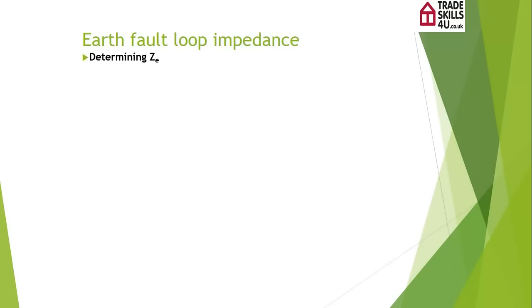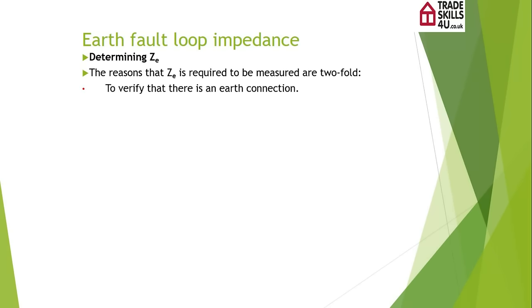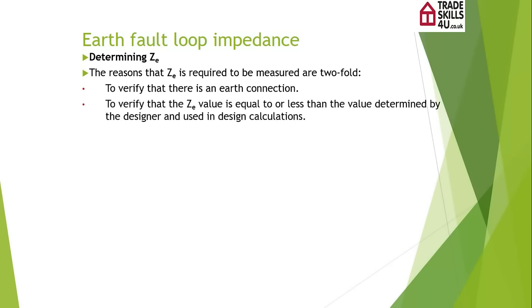Just to recap, the reason that we're doing a ZE test is twofold. We want to make sure that there is an earth connection to the installation, and secondly, that the ZE value is equal to or less than the value determined by the designer and those values quoted in the on-site guide by the distribution network operator.